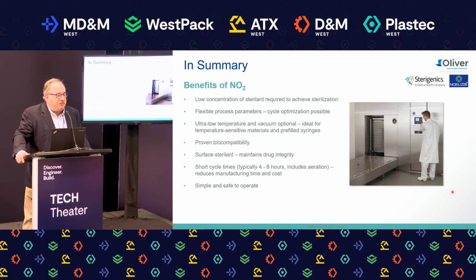So again, the benefits of NO2: it needs very little concentration for efficiency. So it's very efficient when you look at how much is needed for dosing to sterilize your product. The other point too is that the process parameters, the amount of humidity, the temperature, the pressure, the dwell, all of those are product specific. So we have a lot of flexibility in that we can maximize the sterilization process for both the physical properties as well as the sterilization requirements for your particular product. And we do that through feasibility studies and development.